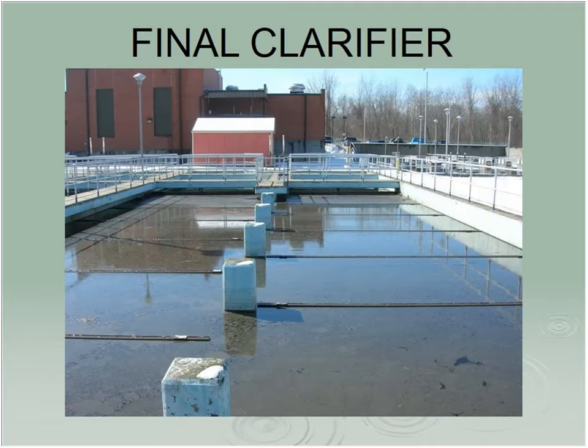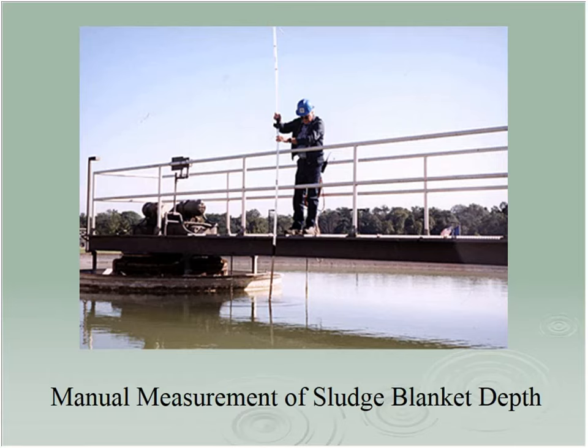Take a good look at that picture. Does that look good to you? That's why I don't recommend rectangulars on the secondary. This is Wallingford, Connecticut, about 6 years ago. I was just staring at that thing. The operator came over and says, oh yeah, there's no problem with that. We're good. That was my clarifier. Go back home and call it sick for the day. Terrible thing.